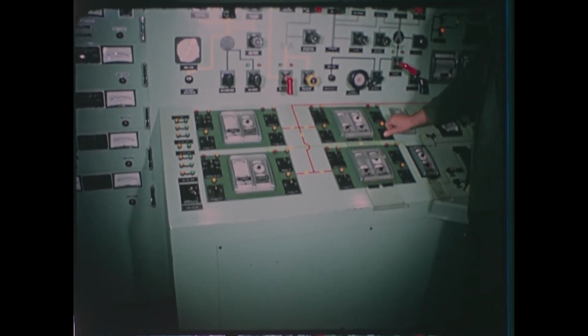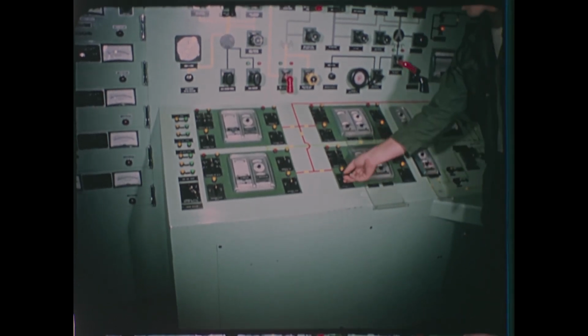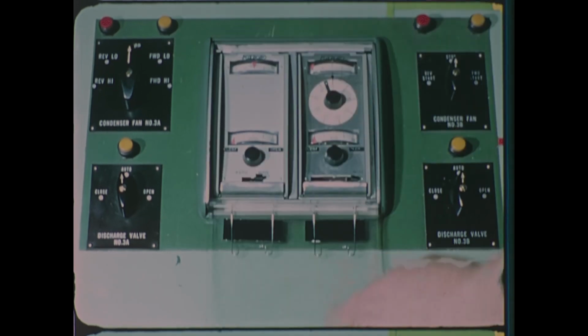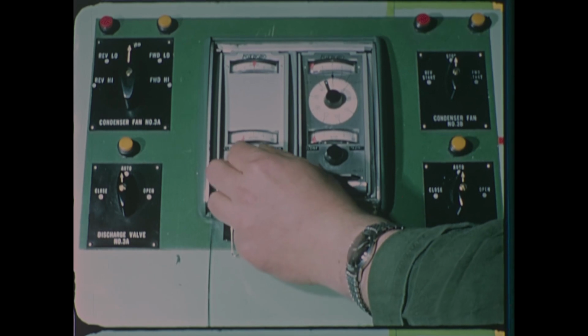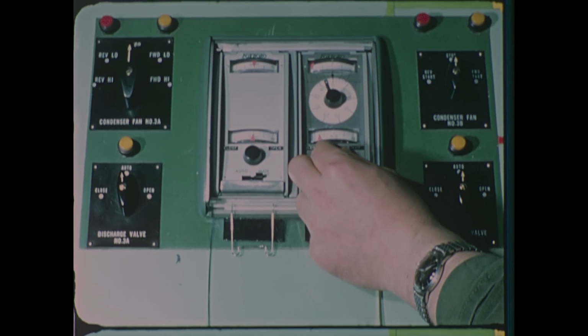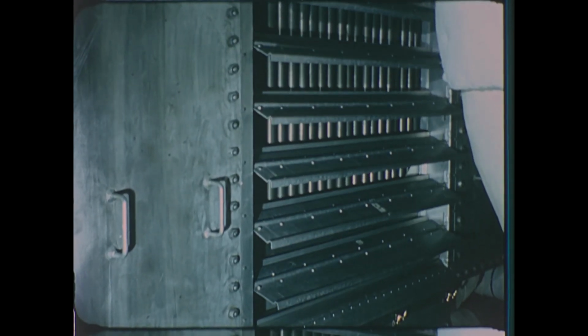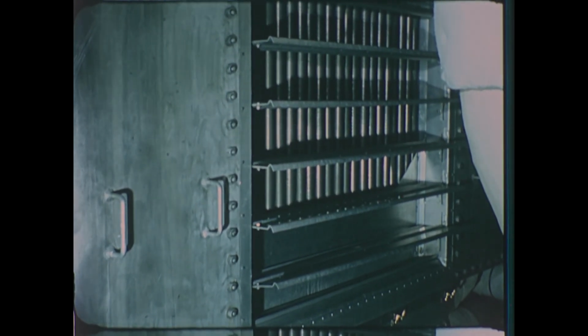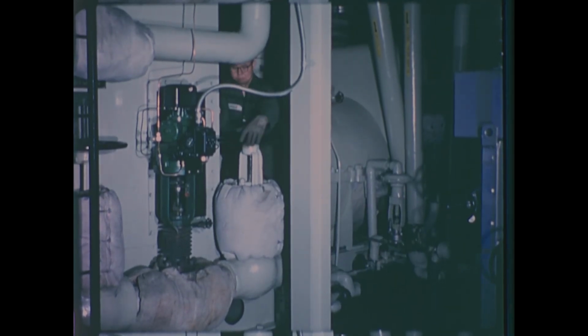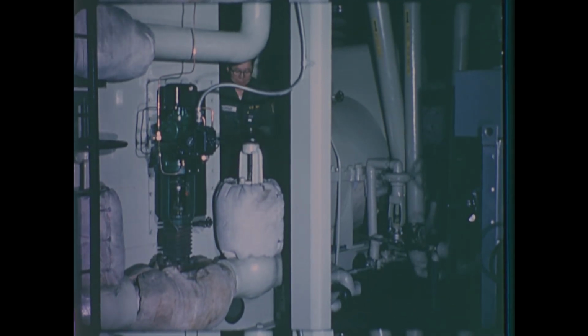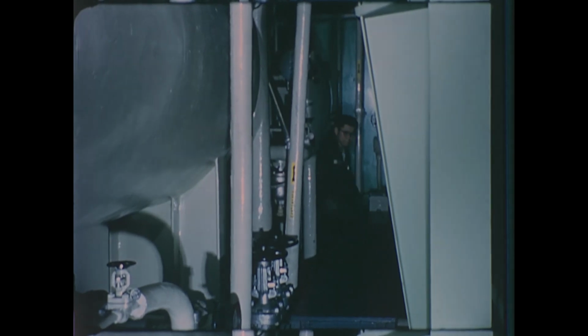The control room operator checks with the equipment operator to ensure that the condenser air discharge valves are operational and checks the operation of the condenser main bank louvers. Next, an operational check of the air cooler section louvers. These operational checks are monitored by the equipment operator. Returning to the secondary building, the operator proceeds to open the isolation valve at the desuperheater steam flow controller. The system is now ready for the establishment of vacuum in the condensers.